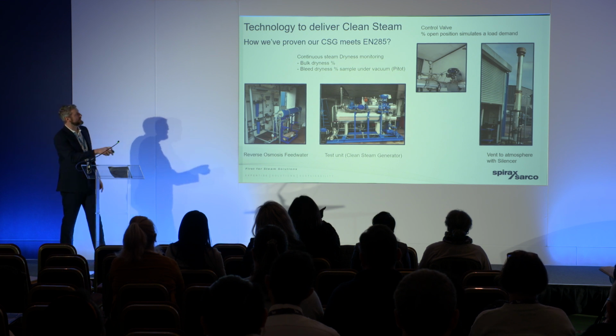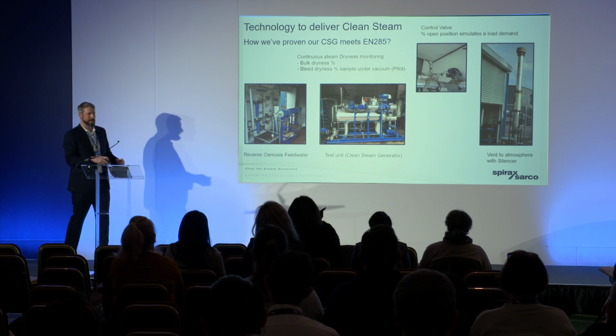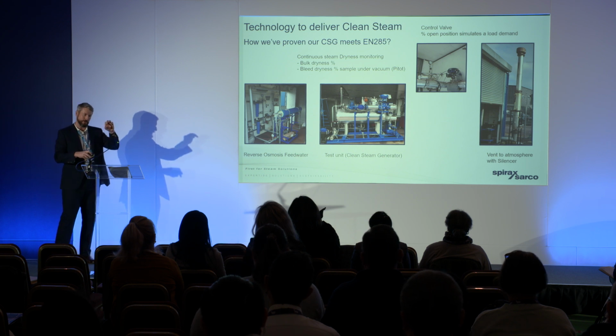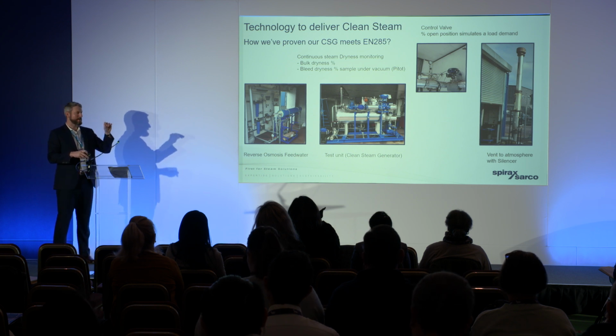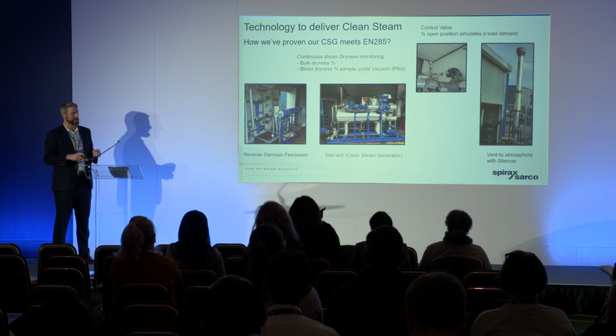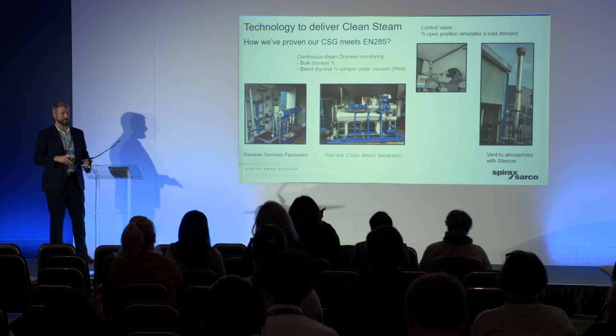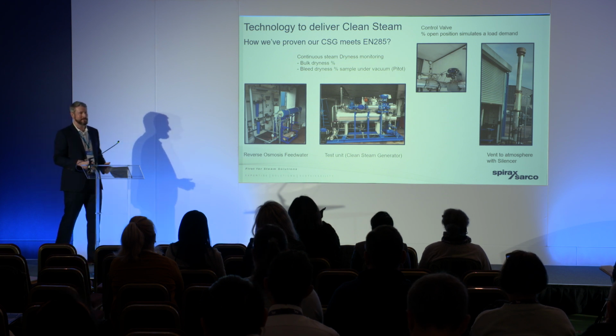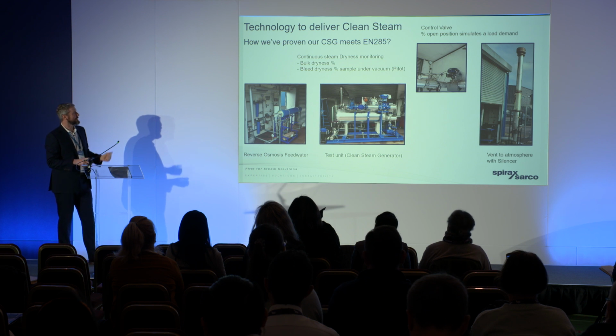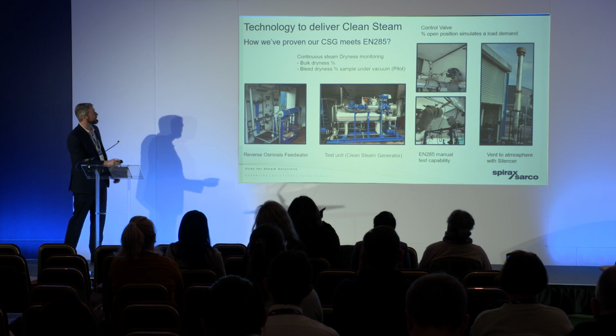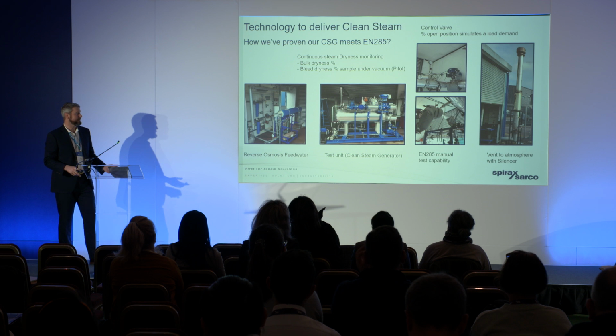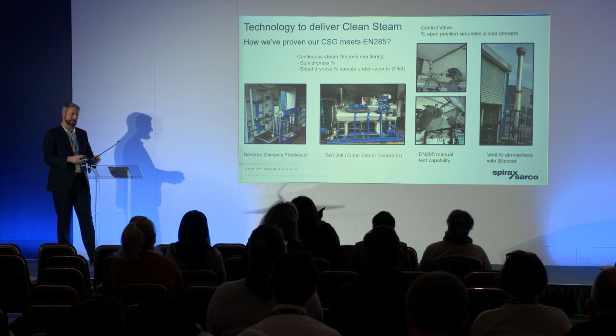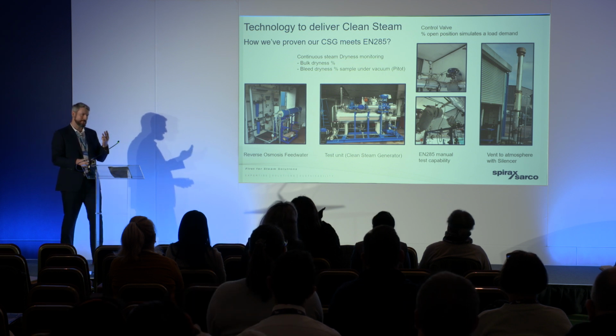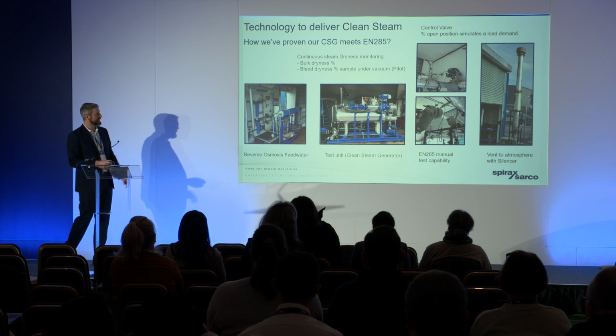So we did a second means of testing with a pitot tube, and we put compressed air through an ejector, which created a vacuum. With that vacuum and a higher differential pressure, we were able to measure down to 94% steam quality. We also had our EN285 manual test capability, which we were intermittently testing. So we had 3 different ways of testing our dryness.